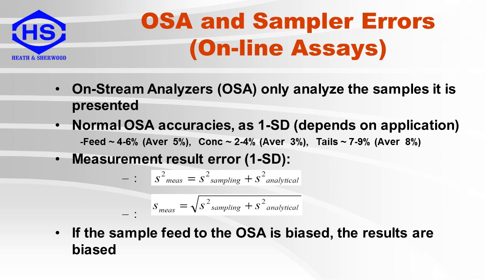On-stream analyzers only analyze the sample presented to them. The one standard deviation measurement errors of analyzers are a combination of the sampling error and the analytical error of the instrument. The measurement error can be determined by summing the square of these errors and then taking the square root of the sum. It should be noted that this sampling error is the fluctuating bias or the precision error. In addition, as the sample fed to the OSA has a constant or systematic bias, the results will also include this bias.